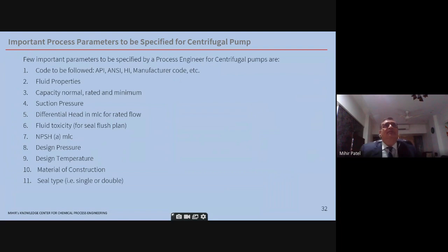Now, important process parameters to be specified for a centrifugal pump by the process engineer. As you can see, the code to be followed: API, ANSI, Hydraulic Institute. API 610 is the code. These are very robust pumps. They run for many, many hours without failure. ANSI pumps are smaller, normally for chemical services. And API pumps are almost 1.5 to 2 times costlier than ANSI.